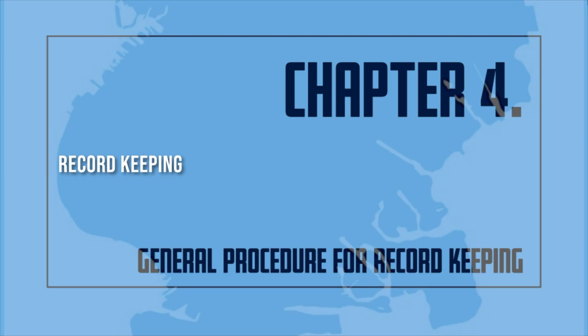Records. Fire Code 901.6.2. Records of all system inspections, tests, servicing, and other maintenance required by the New York City Fire Code, New York City Fire Rules, or the referenced standards shall be maintained on the premises or another approved location for a minimum of 3 years and be made available for inspection by any fire department representative.